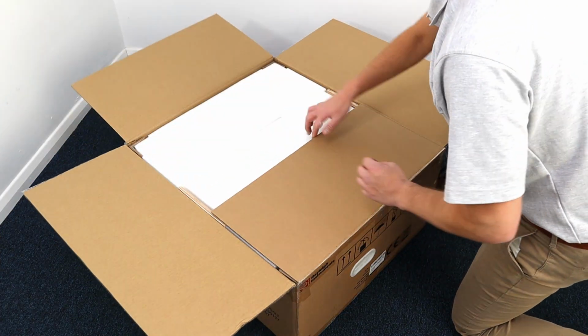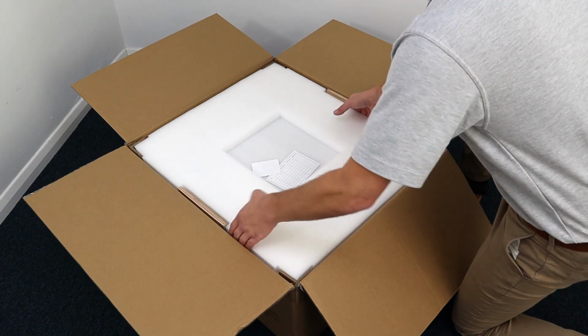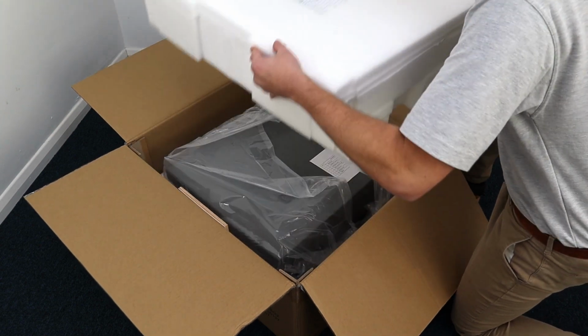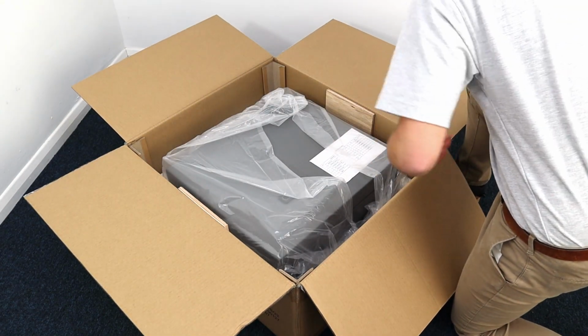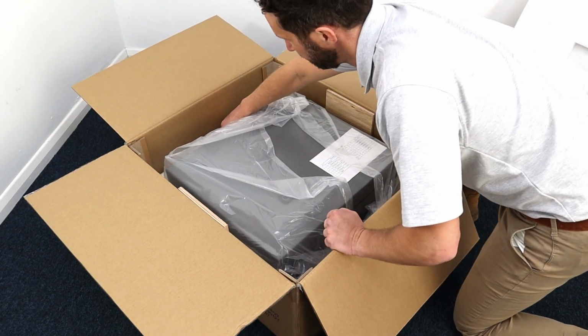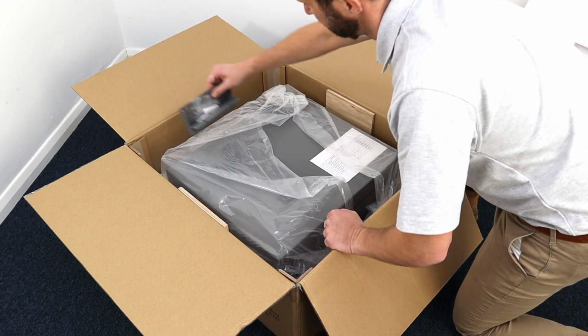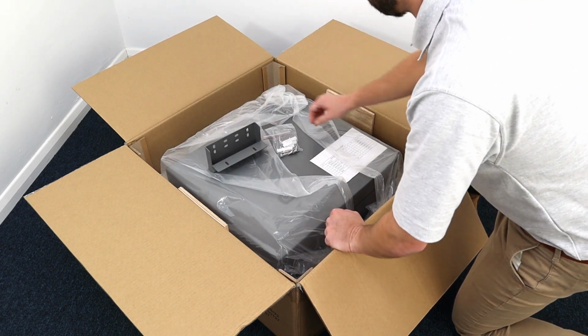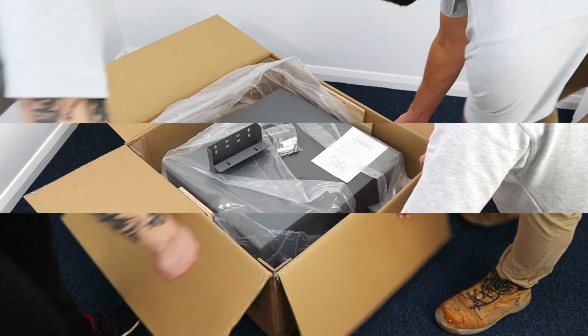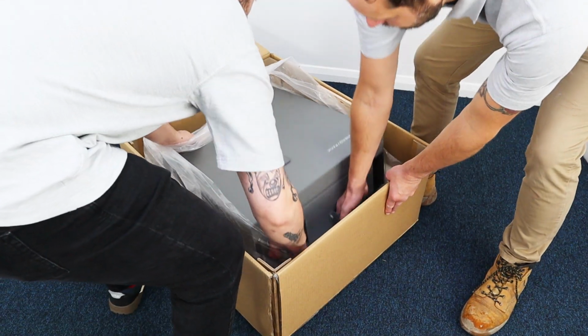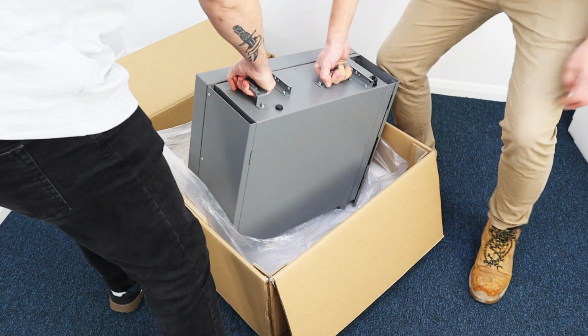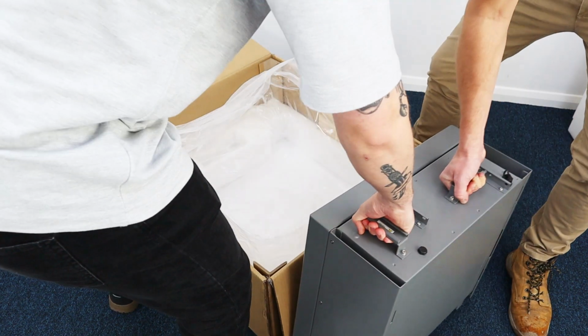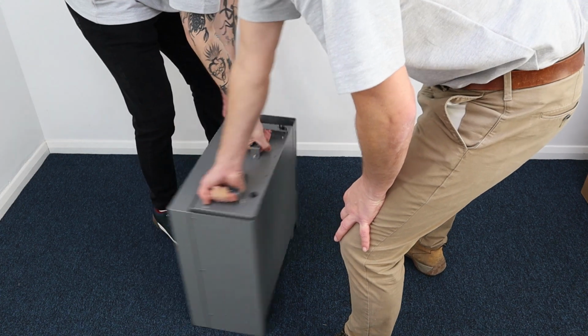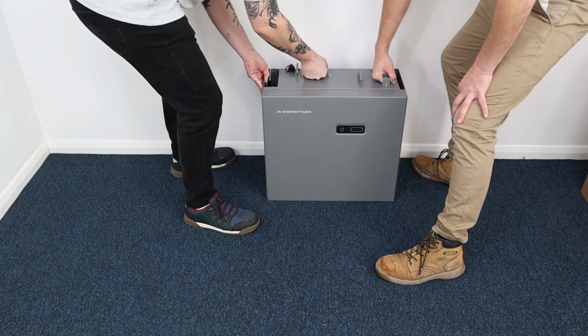Start by unboxing one of the modular battery units. Locate the fixing bracket and fixing screws and put them to one side. Remove the battery unit from the packaging. We recommend that 2 people carry out any lifting of the battery and inverter units to avoid injury due to their weight. Place the battery in the location that you want it installed.